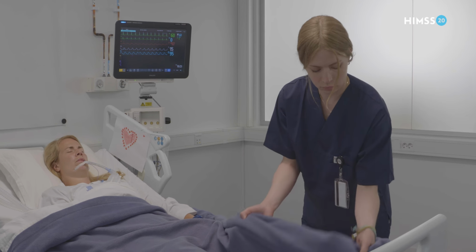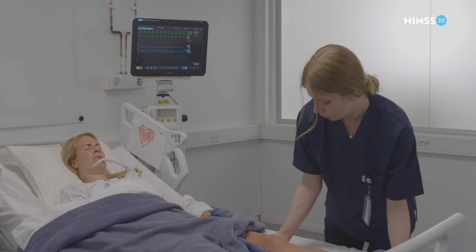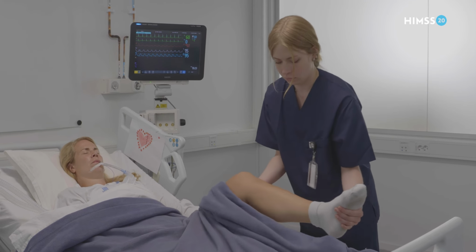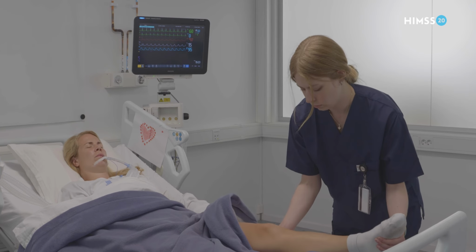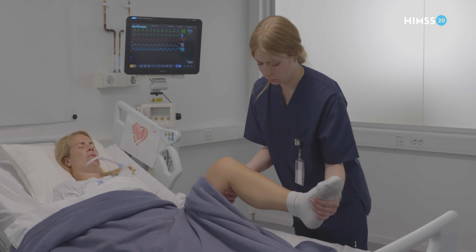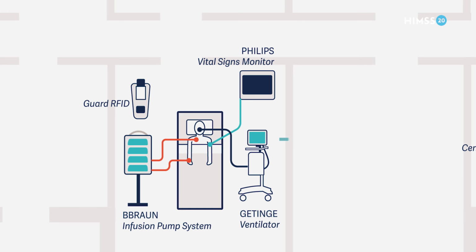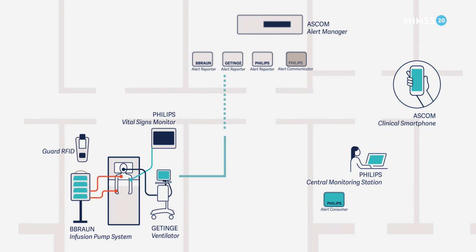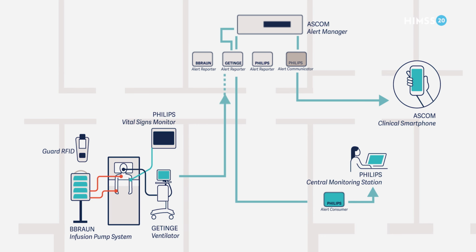What we saw here was Olivia accidentally disconnecting the communication between the Getinge ventilator and its alert reporter. If an actual alarm condition would have occurred while the device was disconnected, our fallback functionality would have triggered an audible ventilator alarm in the ICU room. Once the connection with the Getinge Servo-U ventilator is lost, its alert reporter discovers this and sends a disconnect alarm to the ASCOM Alert Manager, which passes it on to the ASCOM Myco 3 smartphone and to the Philips Central Monitoring Station. When the connection is re-established, the ventilator sends an alarm update message confirming this to the alert reporter, which passes the message on to the ASCOM Alert Manager. The alert message is also inactivated at the ASCOM smartphone and the Philips Central Monitoring Station.